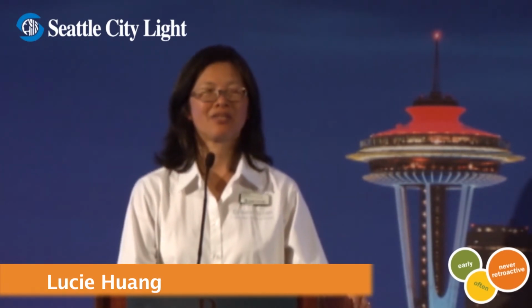We want 15-minute increments with the same timestamp for all the parameters, so that if an assumption is built into the controls, like a certain pressure in the duct meaning the fan runs at a certain speed, we can make sure those line up and the assumptions built into the spreadsheet play out.